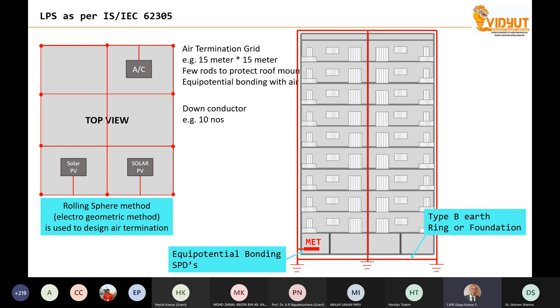The second part of lightning protection is the down conductor. Let us say in this typical example, there are 10 down conductors. Multiple down conductors are necessary because we need to see that the lightning current is divided through different paths.